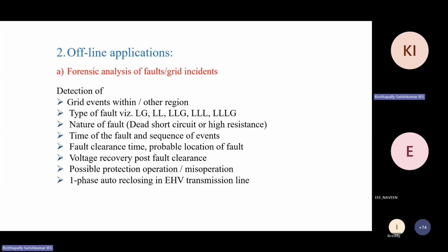Next, the time of fault and sequence of events. In SCADA, as I told, the data comes every 4 seconds. So you don't know within milliseconds or microseconds when the fault was initiated and spread in the power system. So you don't know from where exactly the fault started. But in PMU, you have such accurate data, in the range of milliseconds and microseconds, that you can easily do postmortem analysis, tell exactly the sequence of events of the fault, and also locate the fault location, from which substation it started.